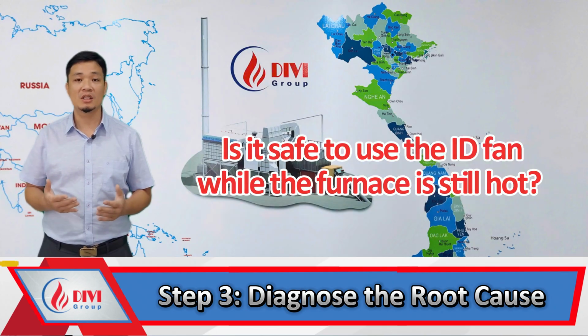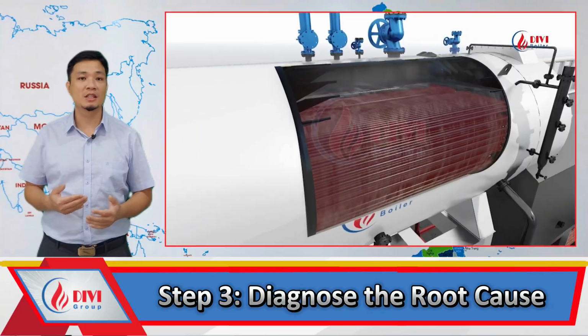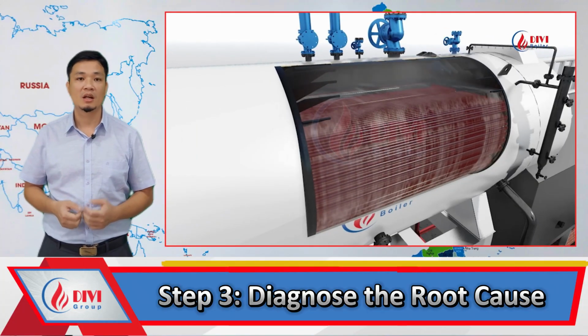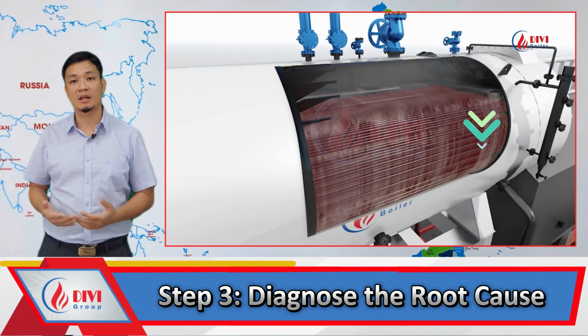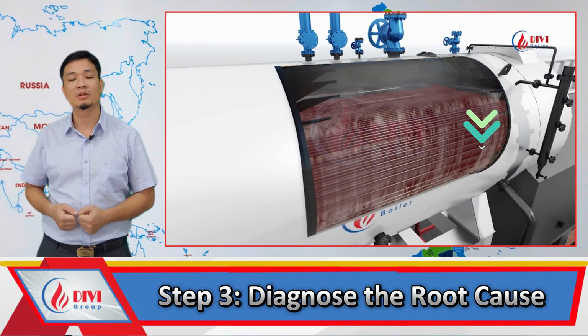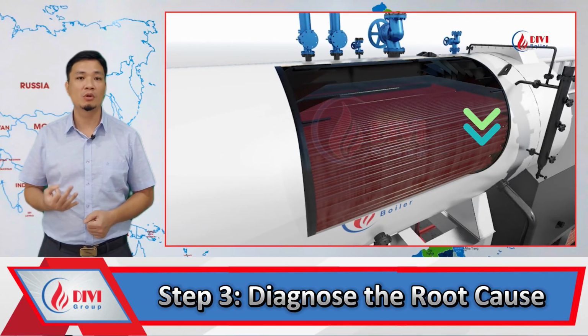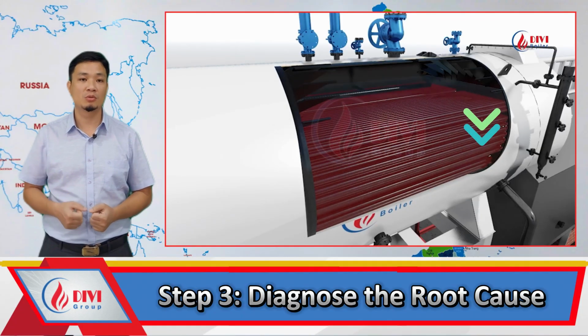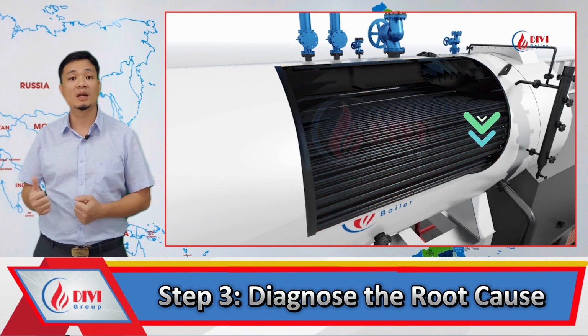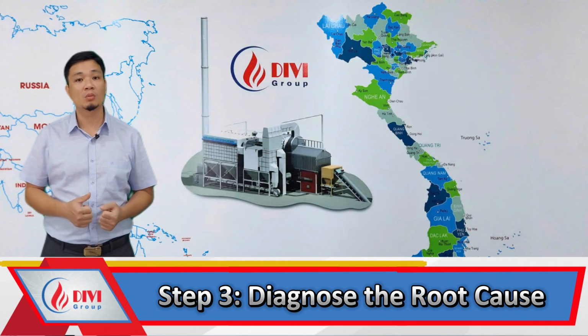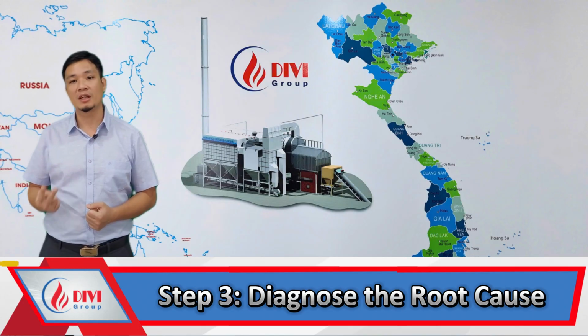Is it safe to use the ID fan while the furnace is still hot? Yes, because the incoming cool air from the fan helps reduce furnace temperature and lowers the heat on the exchange surfaces, thereby preventing further damage to the steam-generating tubes. At the same time, any remaining water inside the boiler will also cool down and cease generating steam.